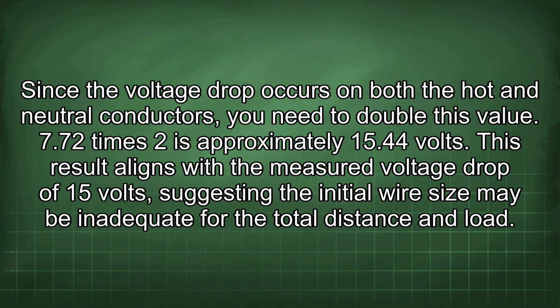Since the voltage drop occurs on both the hot and neutral conductors, you need to double this value. 7.72 times 2 is approximately 15.44 volts. This result aligns with the measured voltage drop of 15 volts, suggesting the initial wire size may be inadequate for the total distance and load.